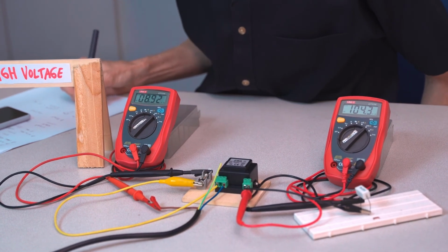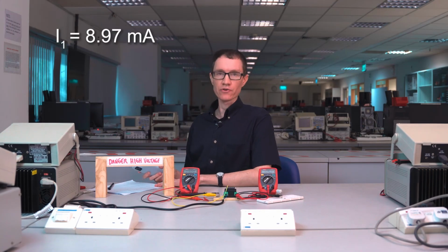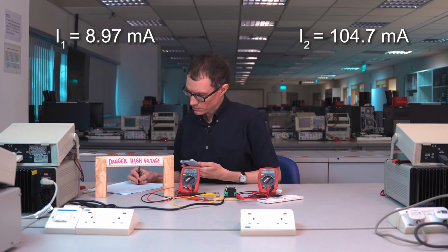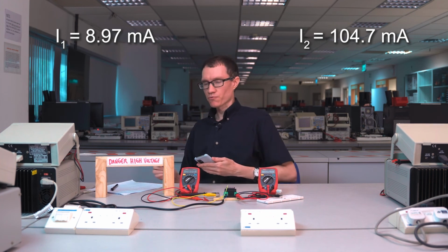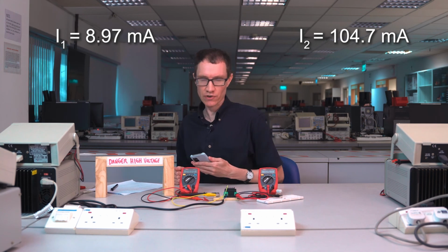It looks like we have about 8.97 milliamps at the primary side and 104.7 milliamps at the secondary side. From these two currents, we can find the efficiency of the transformer.